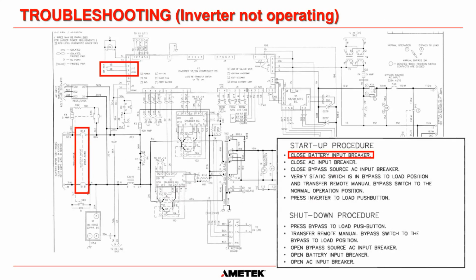Another thing is, if you follow the startup procedure here, and all of our UPS systems have the correct startup procedure on the front of the system on a placard. So you should always follow the startup procedure. For this system, the first item you should do is close the battery input breaker before you even start the charger. And you should have a healthy battery here. So we know that the battery voltage is greater than 105 volts DC. We've measured that. We know that if we close the battery breaker, the system should start.